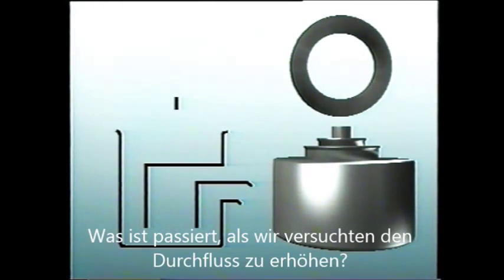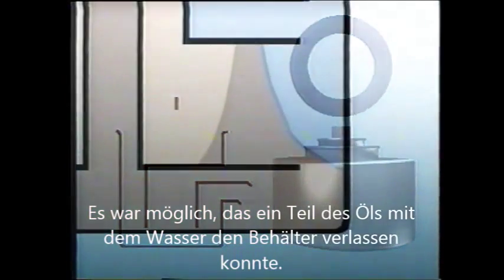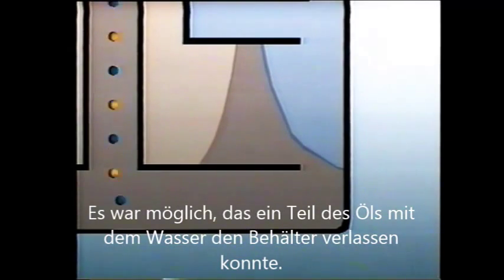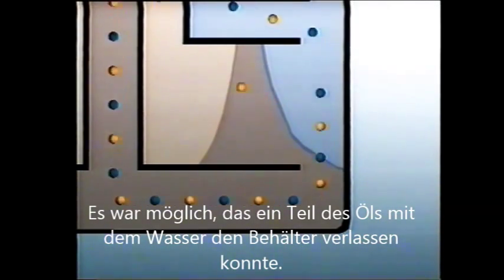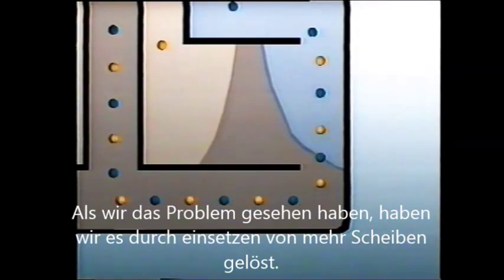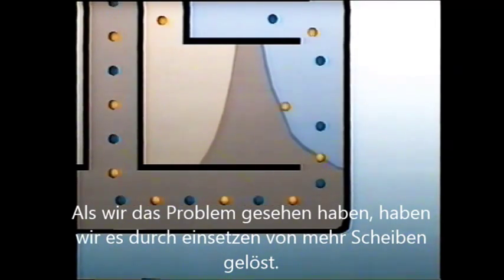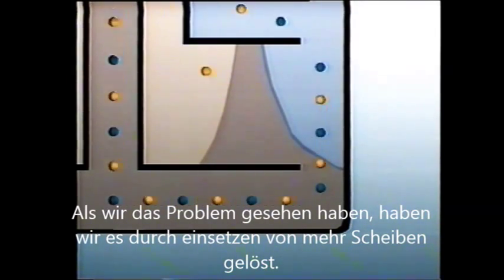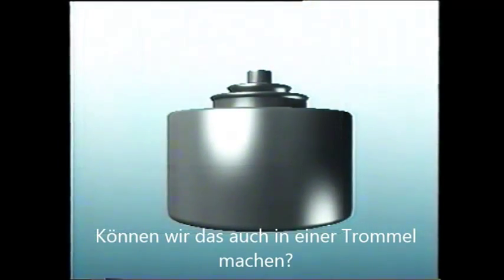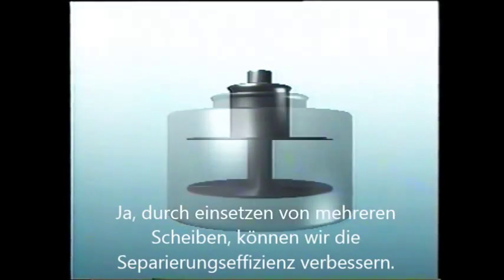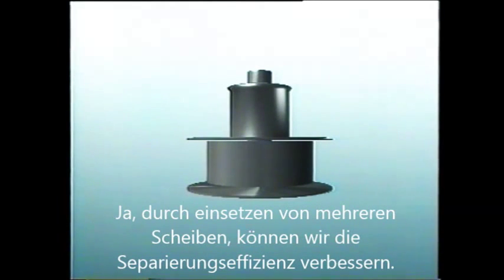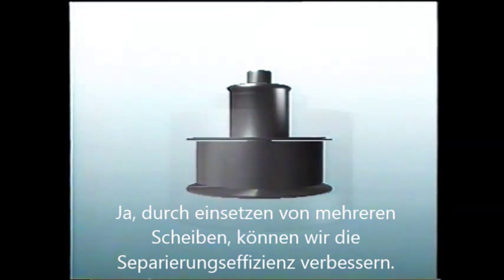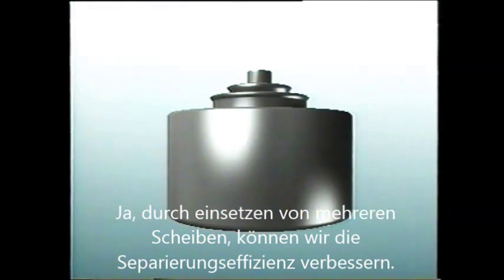What happened before when we tried to increase the rate of feed? There wasn't enough time for separation to take place, so a large proportion of the oil will still be carried out with the water. But when we encountered the same problem before, we solved it by inserting a series of shallow trays. Can we adapt this principle to the bowl? Yes — by turning the trays into cylinders inside the bowl. This greatly improves separation efficiency.